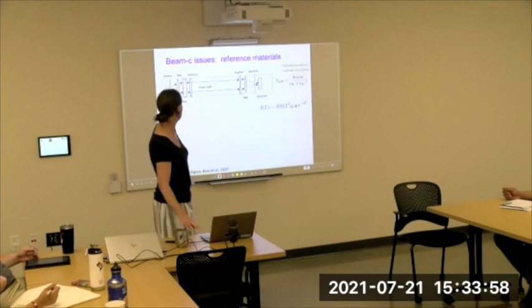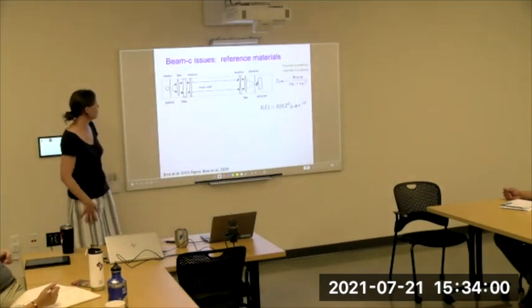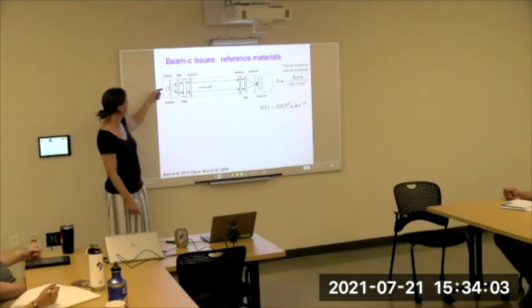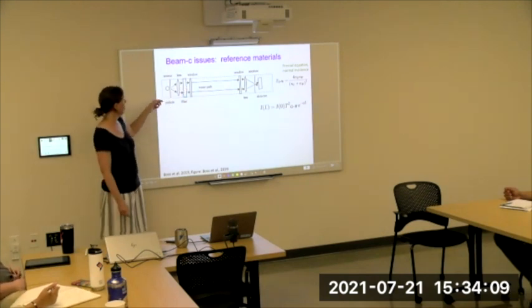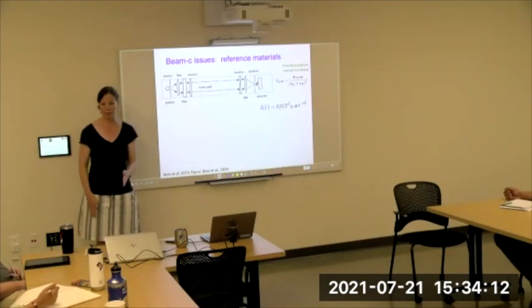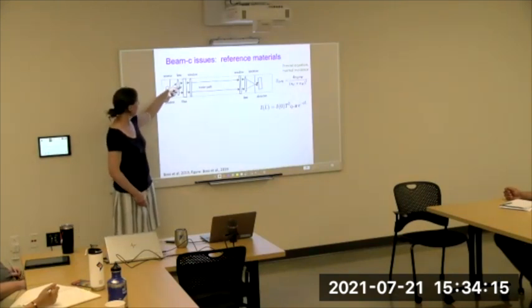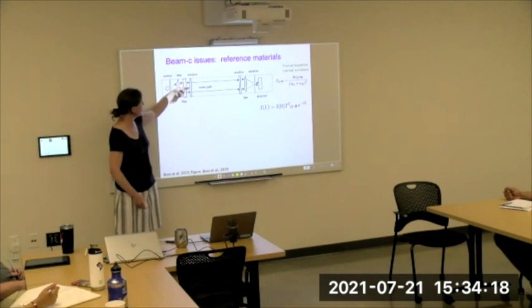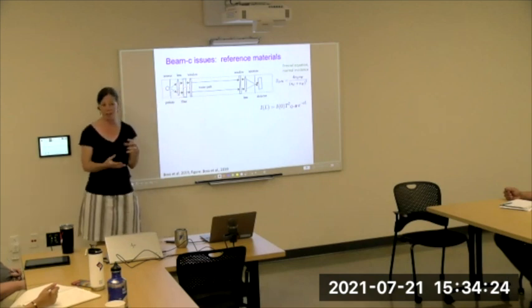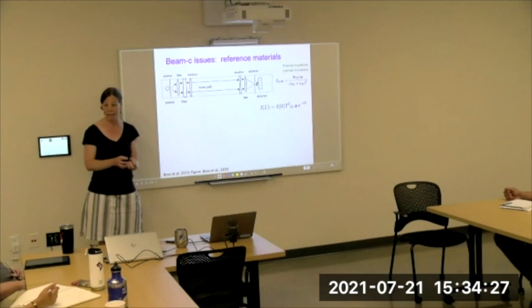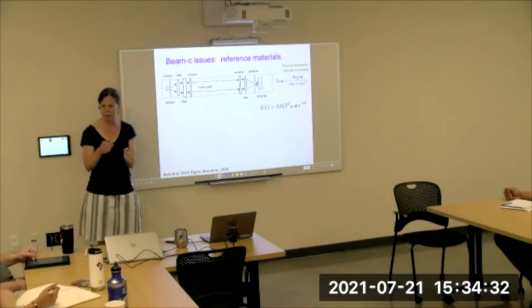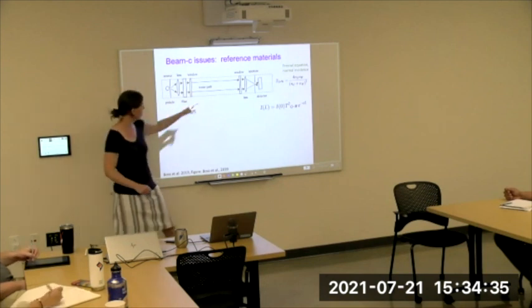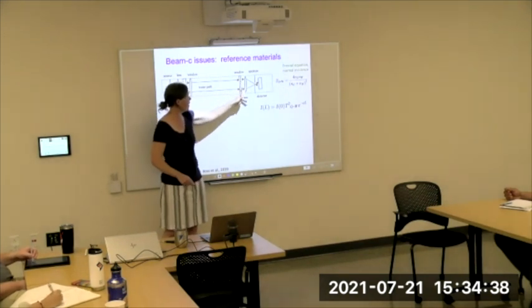So in this situation, what was actually going on had to do with the fact that whenever you're sending light into a transmissometer or a spectrophotometer cuvette, you're passing through refractive index changes as that light beam goes into the window, or the side of the cuvette. You're changing refractive index from air inside the instrument to glass, quartz or whatever. And then you're changing refractive index again as you go from the quartz into your sample or reference water. And then you're changing it again and again.